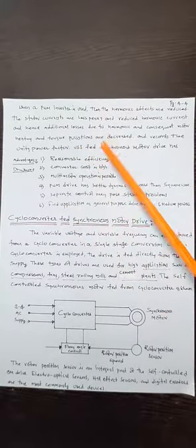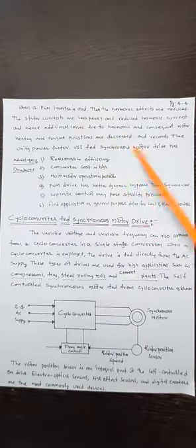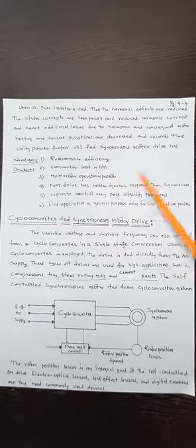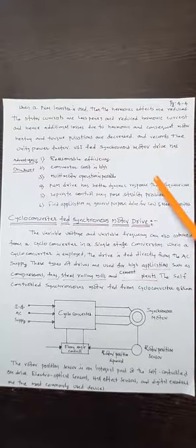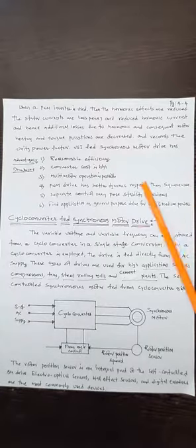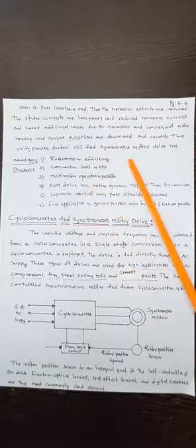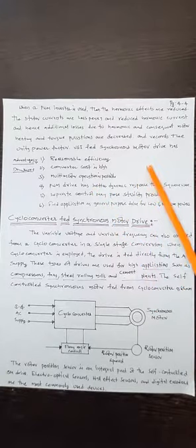Reasonable efficiency is an advantage. Converter cost is high, which is a drawback. Multi-motor operation is possible, an advantage. The PWM drive has better dynamic response than the square wave drive. Separate control may pose stability problems, but self-control avoids this problem. It finds applications as a general purpose drive for low and medium powers. So these are some of the advantages as well as disadvantages of the VSI fed synchronous motor drive.